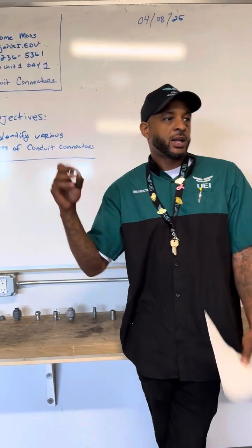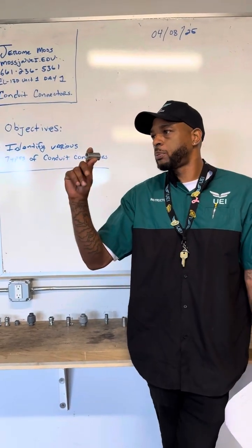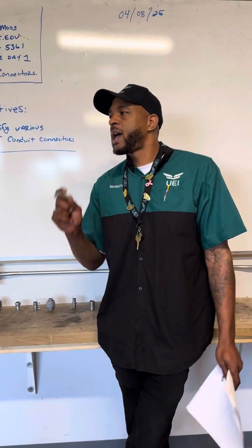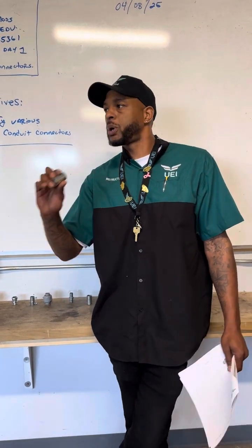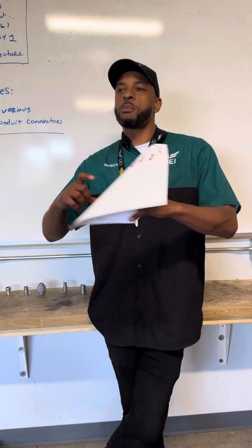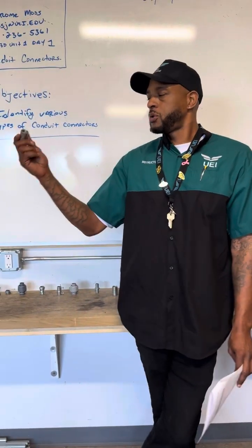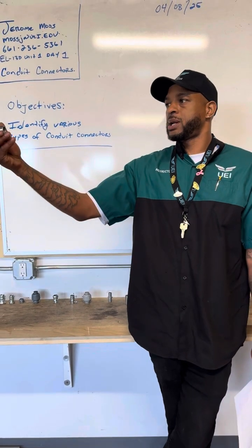And now to understand the difference between this connector, the rigid coupling, and a set screw connector is this. If you're using rigid pipe, 1/2" rigid pipe, you must use a 3/4" EMT bender because the diameter on a rigid pipe is a little bit bigger, okay? So whenever you see rigid, you always know because of the threading inside.